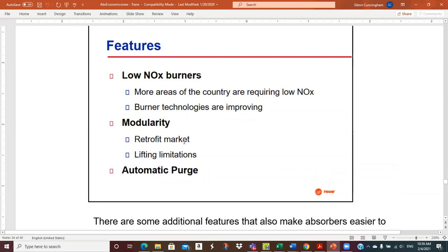Well, one of the main mechanisms that NOx is created is by higher and higher temperatures. The higher the temperature in that combustion zone, the more N2 molecules that are in the combustion air will dissociate into an N and an N. And then there's also O2 in there at high temperature. It'll dissociate. And if the oxygen doesn't get used in the combustion, it's available to combine up with an N that has split apart.